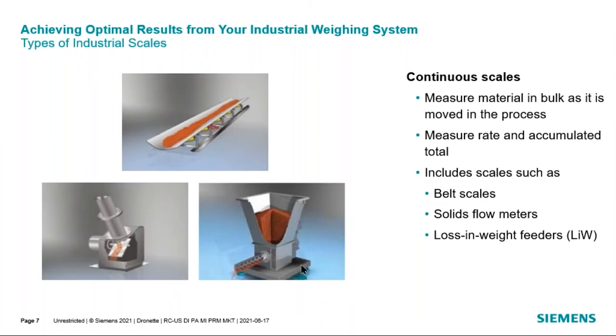The last type of industrial scale is the continuous scale. Continuous scales measure bulk material as it's moved in the process. One thing that makes continuous scales different is they have two measurements: rate — how many pounds per hour or tons per hour are moving at this particular moment — and an accumulated total — how many tons or pounds of product have been transferred since the last time the totalizer was reset.